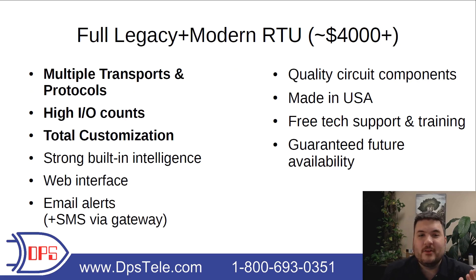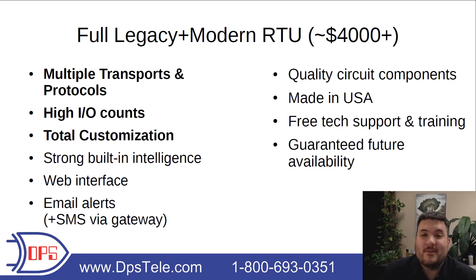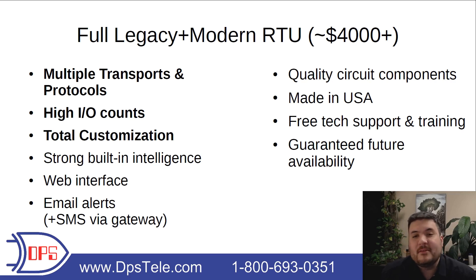To top out the range, the full legacy-and-modern RTU handles both legacy transports and legacy equipment alongside plenty of modern functions. You might have multiple transports — dial modem, serial, LAN, and cellular on one box — with failover from one to another. Multiple protocols let you send to different masters from the same remote. High IO counts are essentially unlimited within reason: 64 or even 80 discrete inputs, 16 analogs, 16 or even 32 relays. Total customization is a given — whatever you need should be able to be designed and built for you.